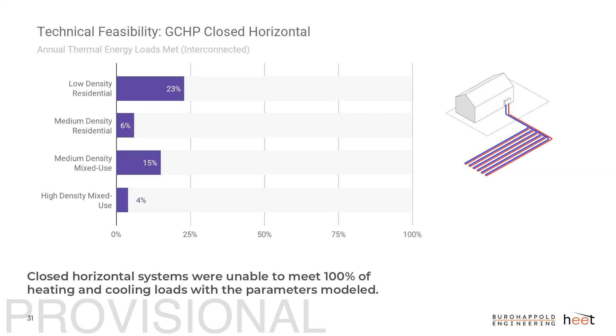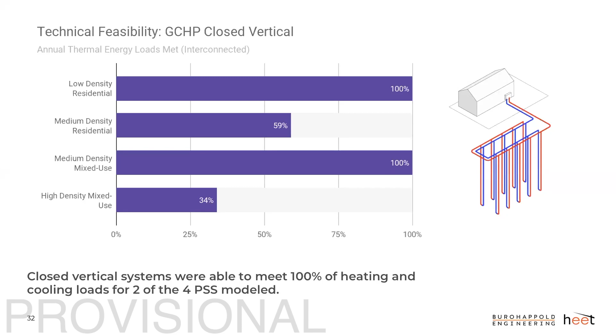The closed vertical system actually performed quite well, so this is a best case scenario. Remember the thermal imbalance I mentioned, this doesn't yet account for that. But if we open it all up, we can meet 100% of heating and cooling loads in 2 out of the 4 prototypes we studied. For medium density residential, you can meet 100% of cooling loads but not heating loads. High density mixed use is pretty difficult, but these are land uses that would already face a lot of problems with existing street infrastructure, so that wasn't a huge loss.